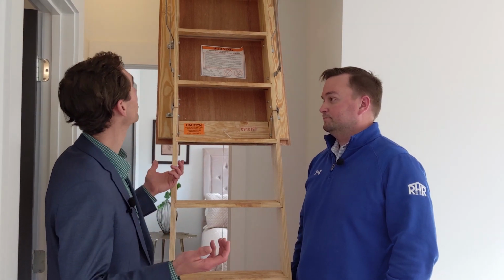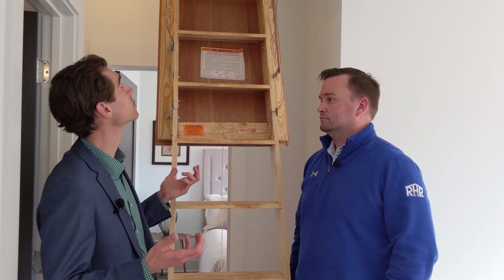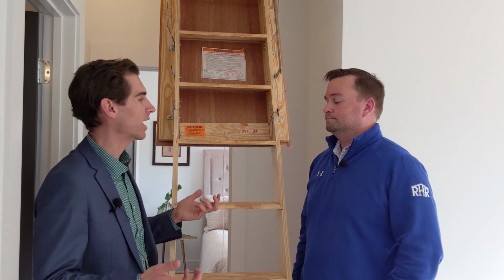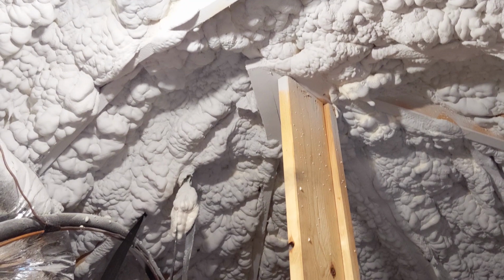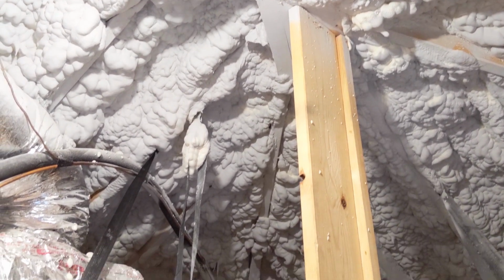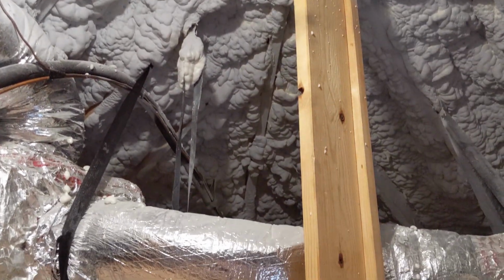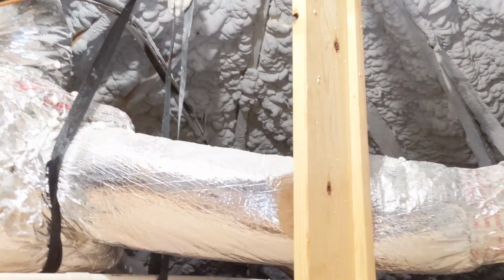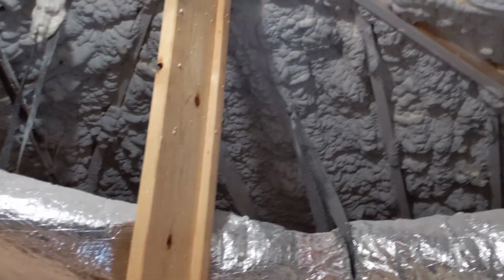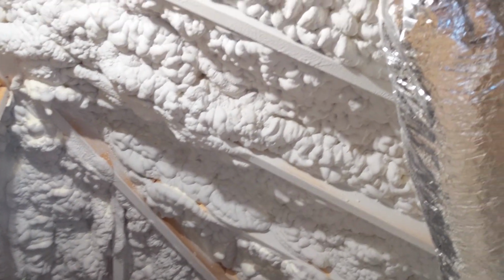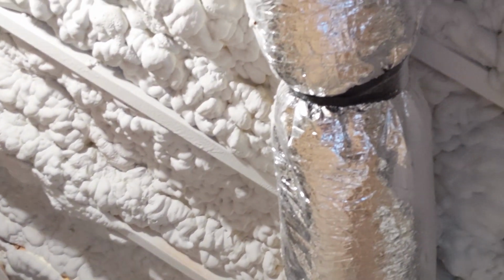The other thing I noticed up there is the ductwork is attached to the roof line of the house. Yeah, we brought the ductwork inside the building enclosure when we put that spray foam insulation along the roof line. So now we're not worried about losing air from the second level up to the attic space, because it's all part of that conditioned space, which allows the ductwork and the HVAC system servicing it to be far more efficient.